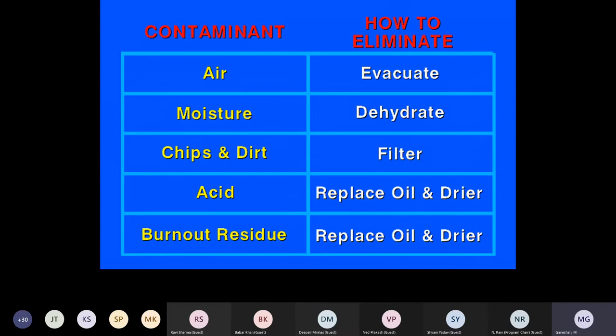We should not have any non-condensable. Air, nitrogen, if anything remains in the system, that is enough to damage your compressor, because when air goes inside, being lighter in weight, while refrigerant has more weight, the air and nitrogen will fill up the whole condenser.